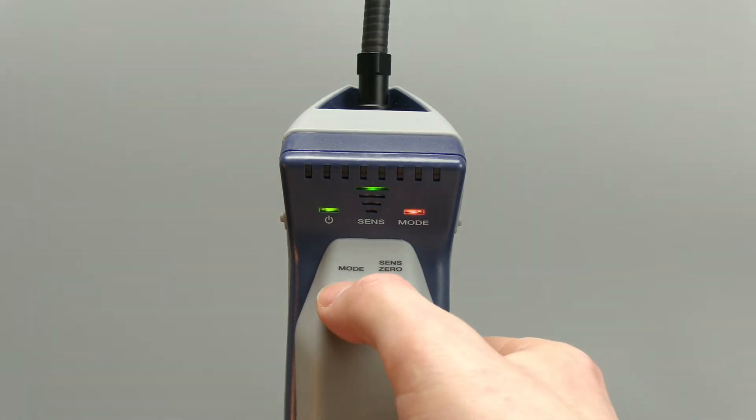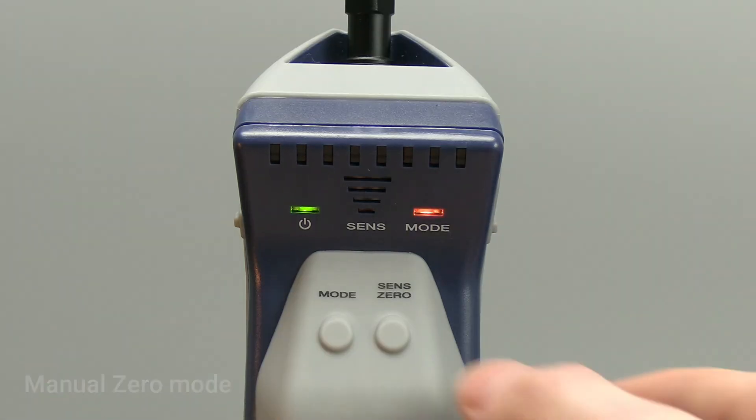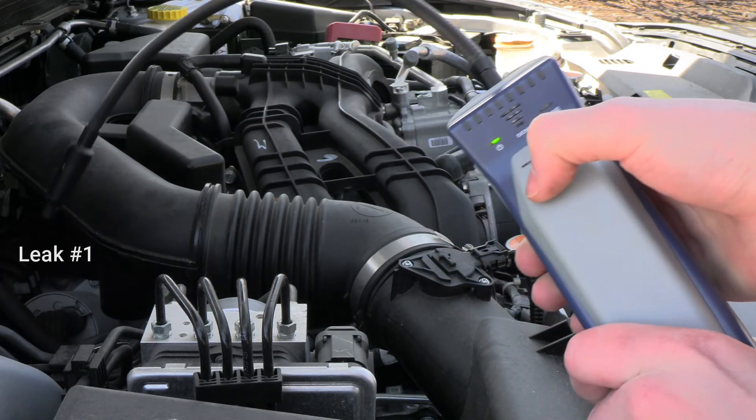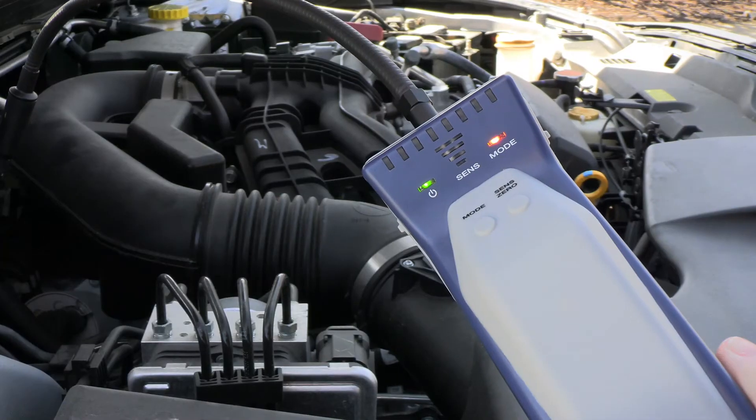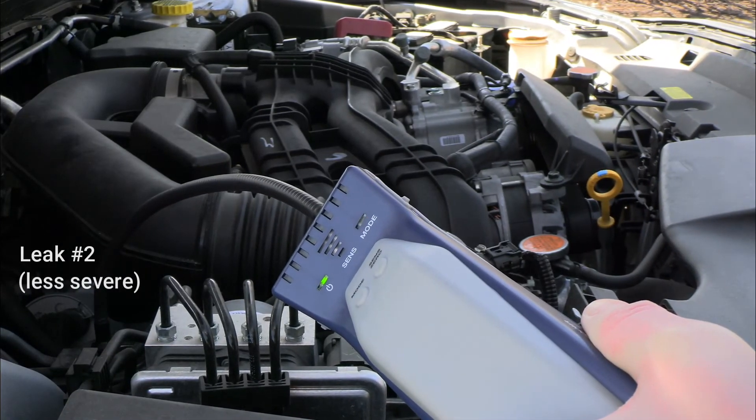In manual zero mode AST 200 IR will only zero to the background refrigerant by pressing the sense zero button. The sense indicators flash briefly to indicate a new zero point has been set. Zeroing sets a new baseline so AST 200 IR will not alarm on a smaller leak size. This can be useful when you have more than one leak and you'd like to identify which leak is larger.